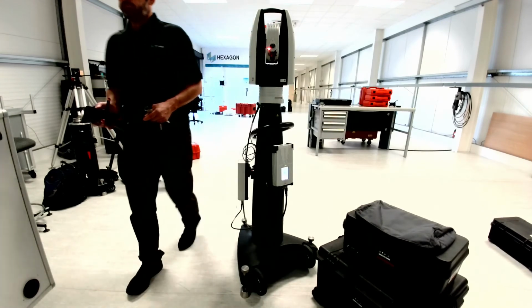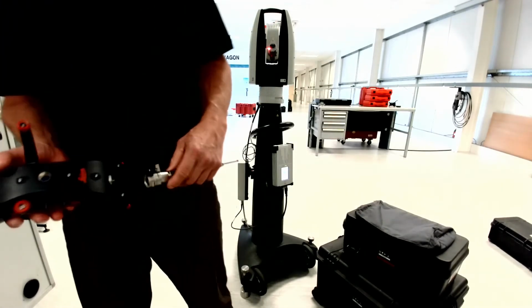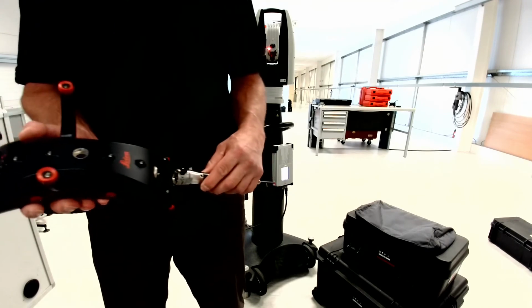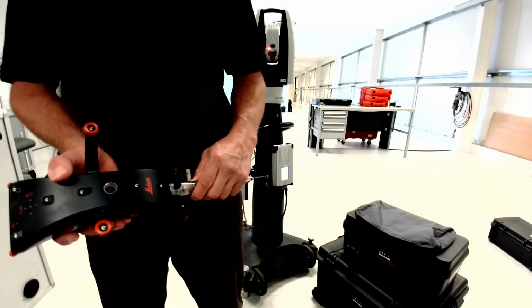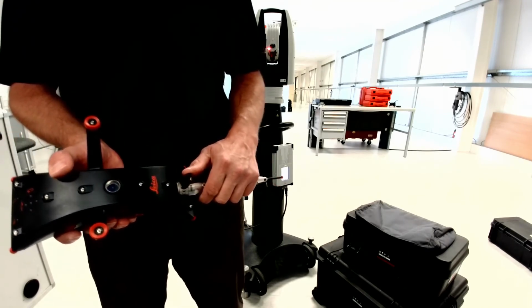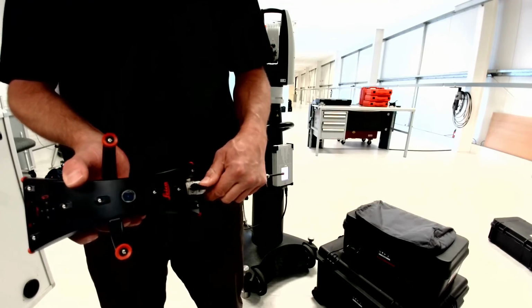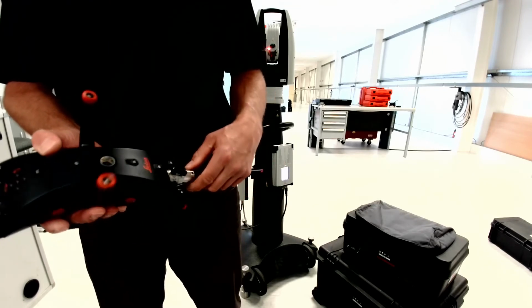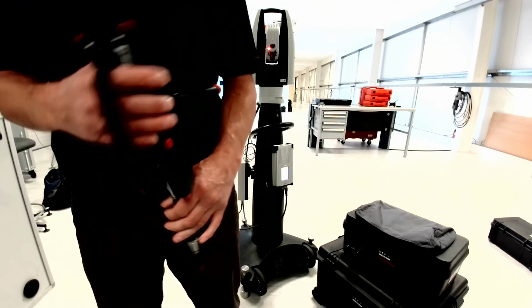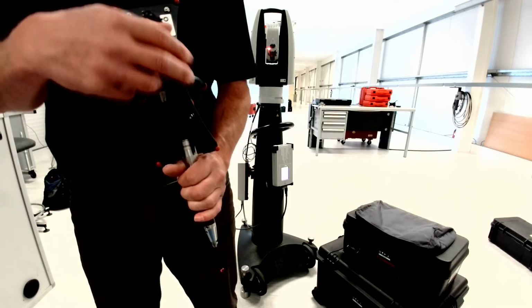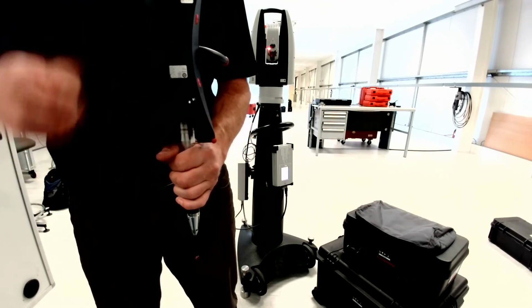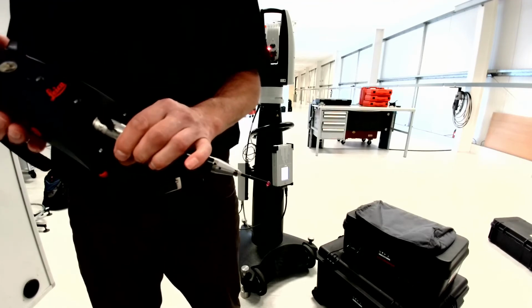Multiple styli, as we've just demonstrated. Barry's going to show you now. You plug your stylus of choice into the repeatable mount on the bottom of the T-Probe, move the handle, and the T-Probe will automatically recognise which probe you've plugged in and send that information back to the controller, so that the offsets for whichever probe you've chosen are selected by the software.